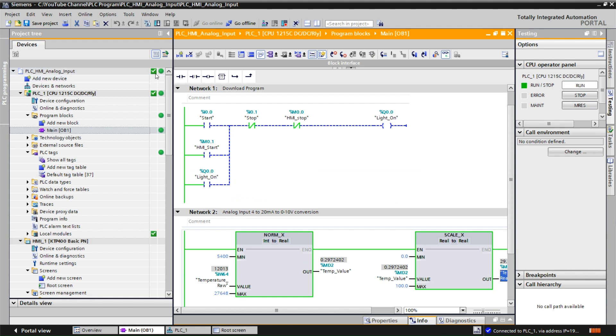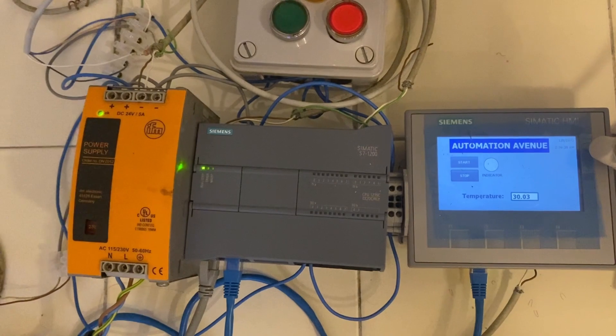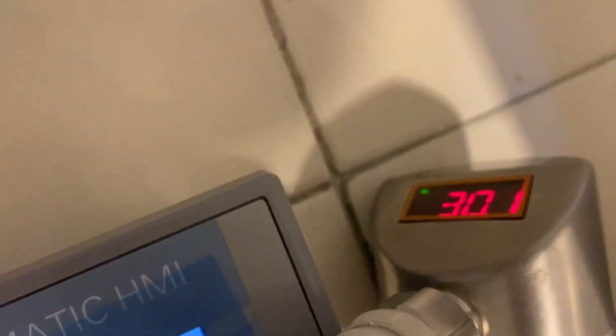You can see everything is green in the online monitor, meaning the program in the PC and the PLC match. You can see NORM_X and SCALE_X are functioning and the output shows 29.72 as the temperature real value. Now let's go to the real PLC and HMI setup — you can see the power supply unit, the S7-1200 PLC, the HMI, and the IFM temperature sensor showing 30.1 degrees C.